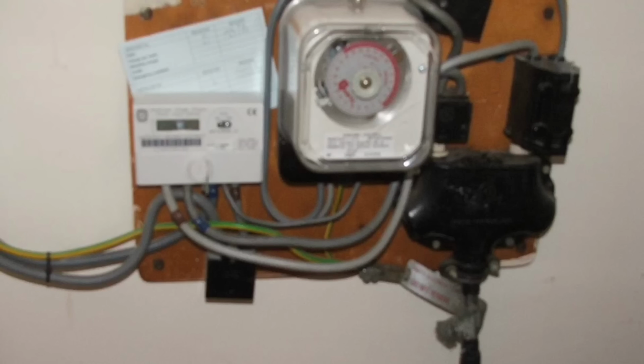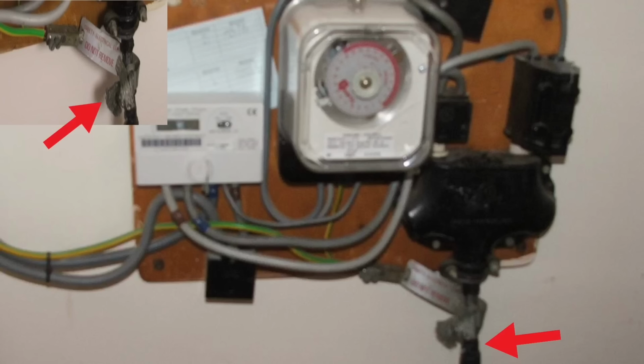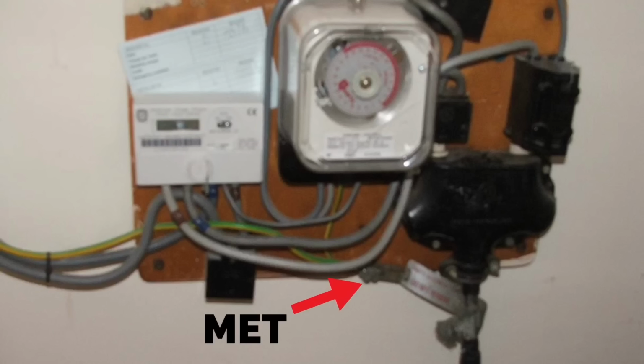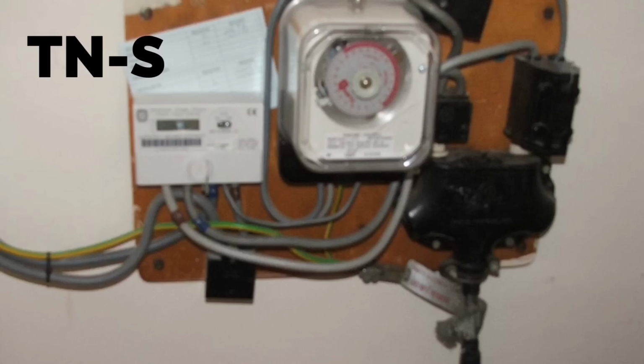So as we look at the incoming cable from the supply authority into the bottom of the cutout arrangement here, we can see there is a connection or a clamp around the outside of this cable, which then takes a conductive material into the MET. This earthing arrangement is TNS. To remind you, T for terra, the French word for earth, N for neutral, and S for separate. So in this case, the earth and neutral are separate from the supply authority's cable.